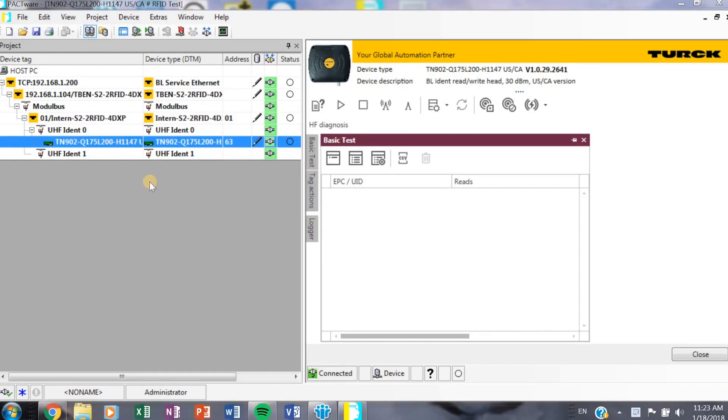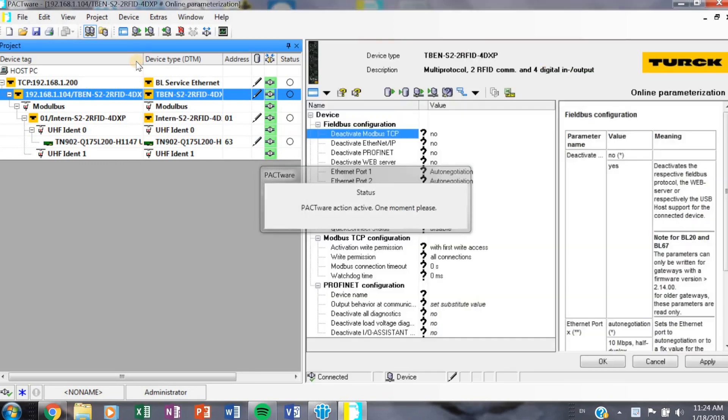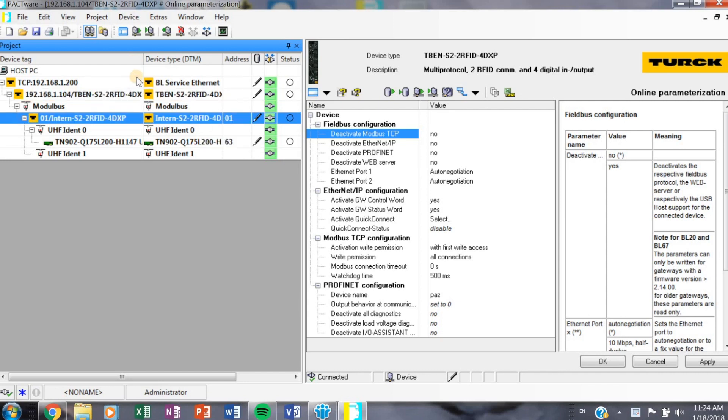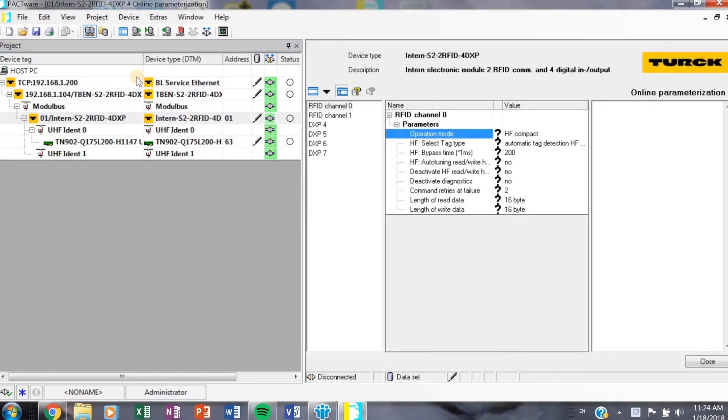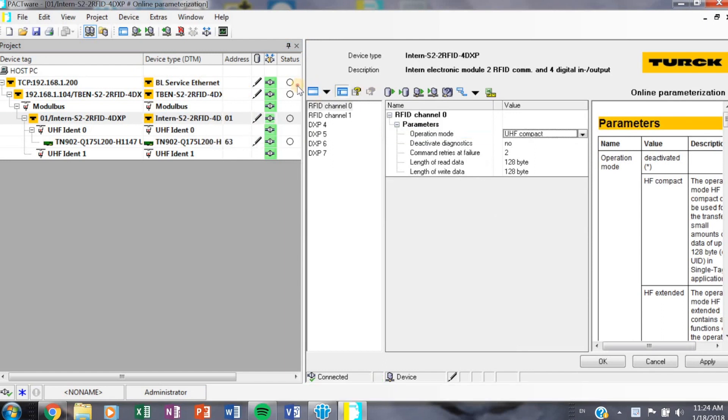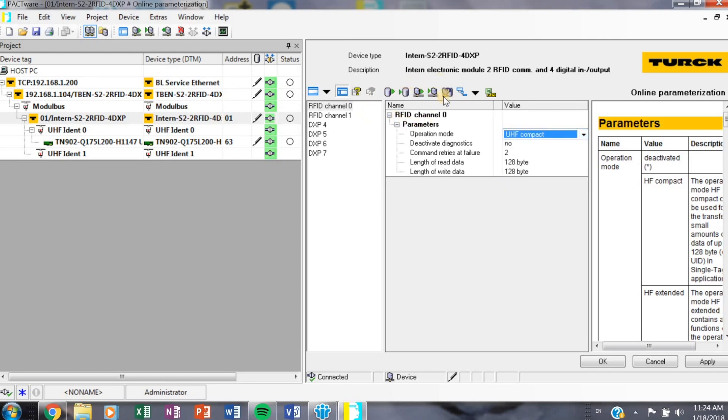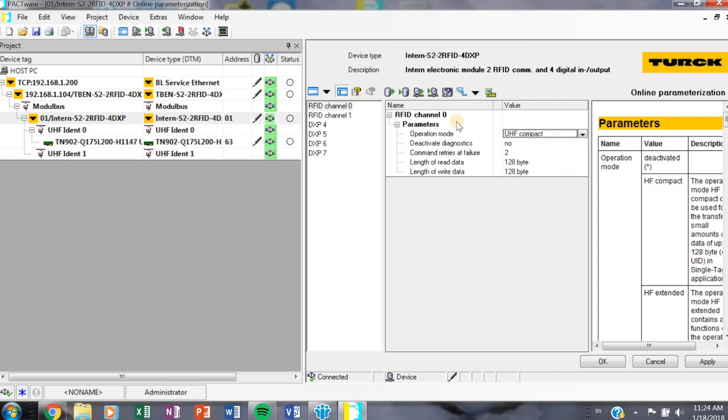Okay, so once you are at the RFID page, what you want to do is make sure if you're using, for example like me, the TBEN-S2-RFID block, those ports, those RFID ports, will take in UHF and HF transceivers. The default is HF, so you got to go back in there, maybe double-click on that, and you'll notice the operation mode. You'll have to change that from HF compact to UHF compact or UHF extended. On the right-hand side, you have your parameter help menu that can help you navigate what each operation mode means. Go ahead and make that change if you have to, and don't forget to power cycle your whole system and get back online with it.